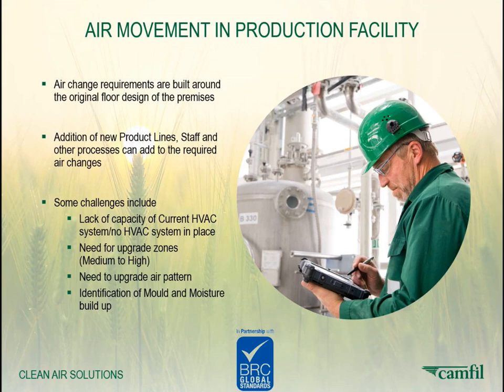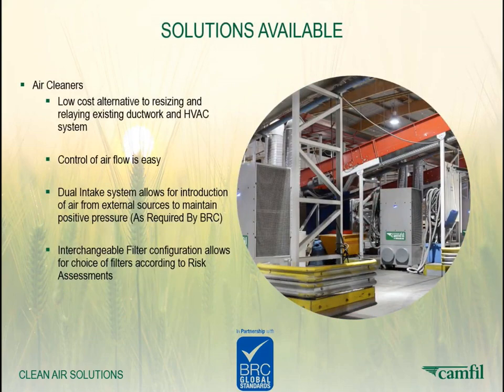Some of the challenges: lack of capacity of the current HVAC system, no HVAC system in place, need to upgrade zones from medium to high, need to upgrade air pattern, identification of mold and moisture buildup. In a lot of areas, we have an air cleanliness solution. It's a low-cost alternative to resizing or relaying existing ductwork and HVAC system. Control of airflow is easy. A dual intake system allows for introduction of air from external sources to maintain positive pressure as required by BRC. Interchangeable filter configuration allows for choice of filters according to risk assessment.